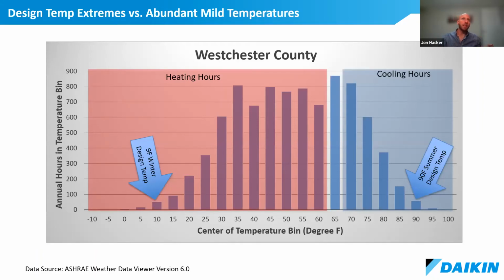And I want to call attention to the difference between design temperatures and how those are used and applied, and the impact on the operation, right? So we talked about the design temperature for Westchester being 9 degrees Fahrenheit. That's actually the 99.6% design temperature for heating for that location. So that means 0.4% of the hours of the year, or about 35 hours, will be below that temperature, which is very rare. If you're looking at this graphic, there are not a lot of hours in the year below 10 degrees Fahrenheit outside. Mechanical contractors and design firms will size HVAC systems for these extreme conditions. They kind of have to. That's the engineering practice. But the reality is that the majority of the time these systems operate, they're not operating at that high of a load. We saw that load diminishes as we get to more mild conditions, right? So in Westchester during the heating season, more than 80% of the hours are above 30 degrees Fahrenheit outside, right?